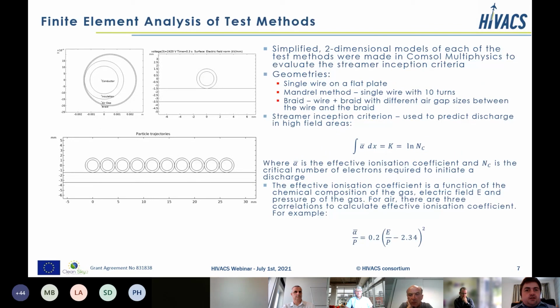So in the second part of this, we try to understand some of the origins of the differences. We did this using finite element analysis. 2D representations were used for each of the test methods. So we've got in the top left picture here is the braid method. A small air gap of 0.5 millimeters was used between the braid and the outer surface of the insulation, or else the braid wouldn't be able to be installed. The flat plate is just a single wire on the grounded metallic surface. And then for the mandrel, this was modelled as 10 turns of the wire.